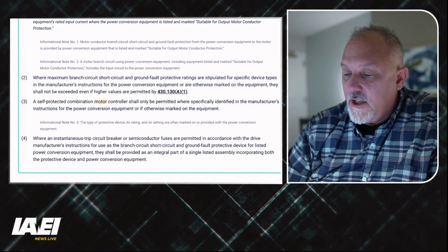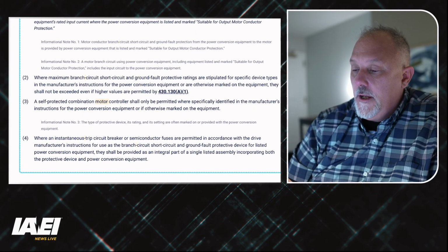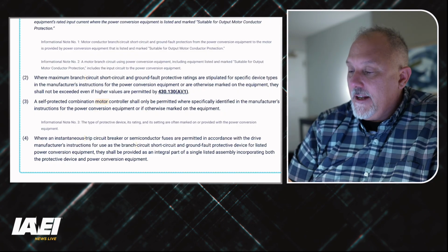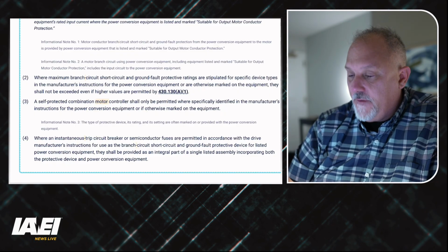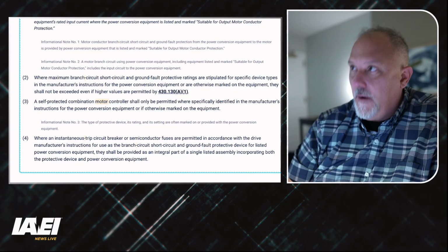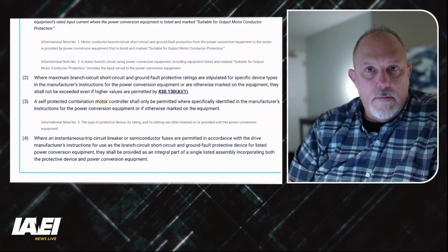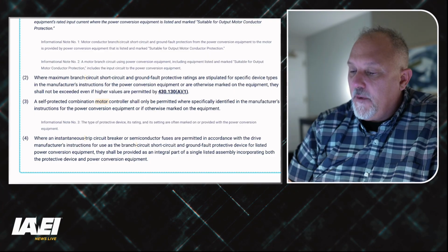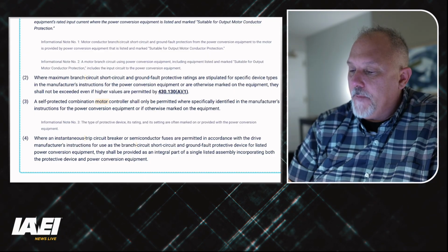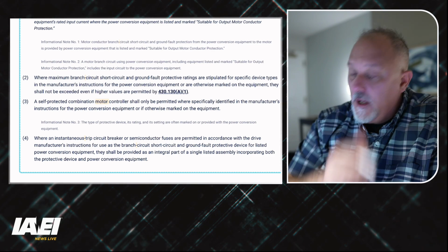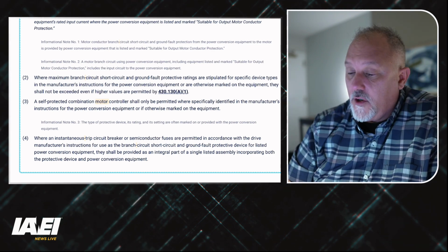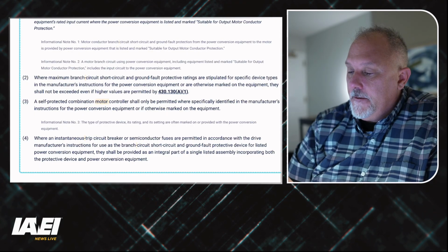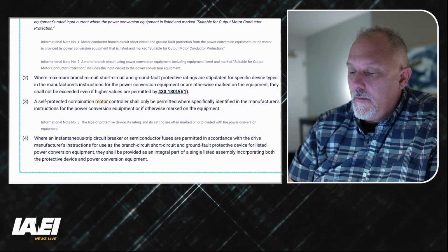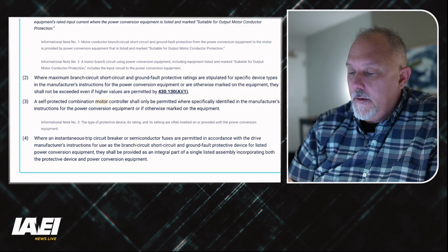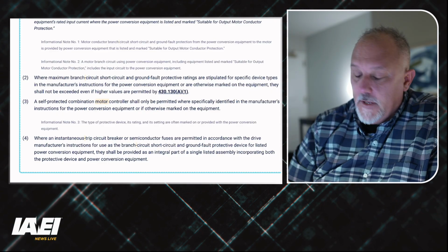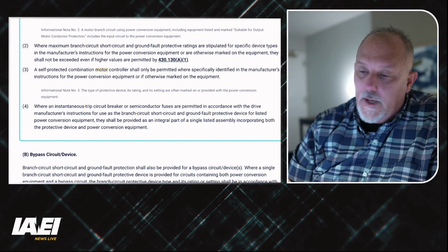And then there's this: a self-protected combination motor controller shall only be permitted where specifically identified in the manufacturer's instructions for power conversion equipment or if otherwise marked on the equipment. What equipment? The type of protective device, its rating, and its setting are often marked on or provided with the power conversion equipment. So they're talking about if it's marked on the power conversion equipment. And then you have the bypass.